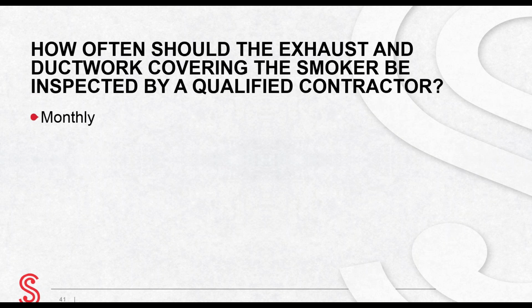The answers that you gave were 10% for annual, 30% for semi-annual, 30% for quarterly, and 30% for monthly. The answer is monthly, D. The exhaust and ductwork covering the smoker should be inspected monthly by a qualified contractor. If the inspection reveals a buildup of creosote and/or grease, then the contractor should continue with the cleaning of the hood, ductwork, and piping.